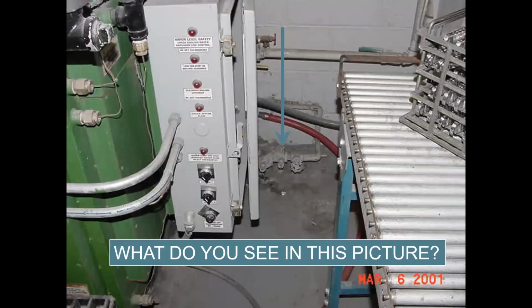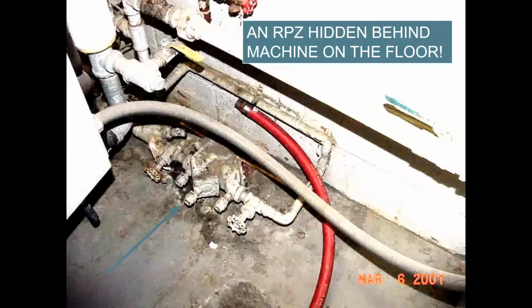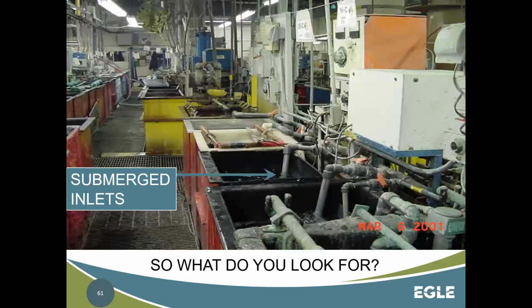So in this case, this was at an industrial center. We've got a close-up on the next slide. There was an RPZ that was installed, but has really been kind of tucked away back here. And it's safe to say, because it was so hidden, and just looking at the condition of that RPZ, I don't think it's gotten much attention. And I would doubt that it's functioning like it's supposed to at this point. So again, this is why when you're going around to some of these properties, it's important to look at, are there things that need to be added? And for what's there, is it still appropriate? Is it still functioning?